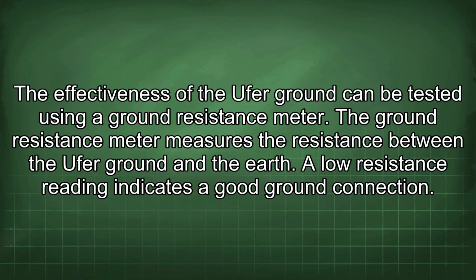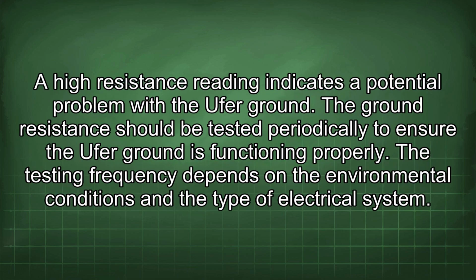The effectiveness of the Ufer ground can be tested using a ground resistance meter. The ground resistance meter measures the resistance between the Ufer ground and the earth. A low resistance reading indicates a good ground connection. A high resistance reading indicates a potential problem with the Ufer ground.